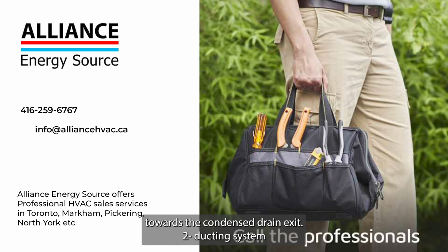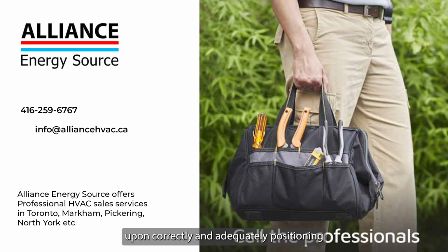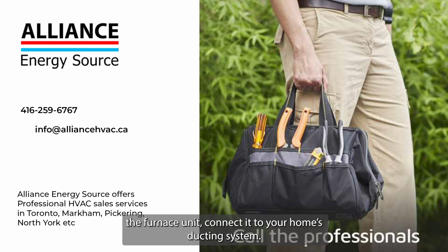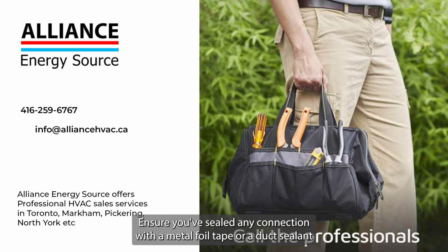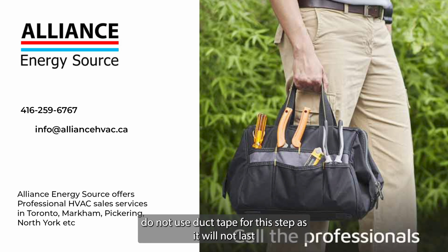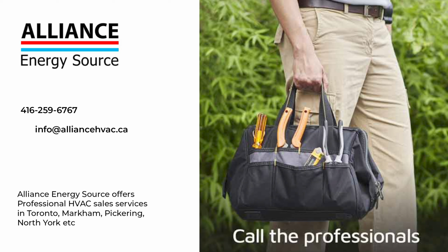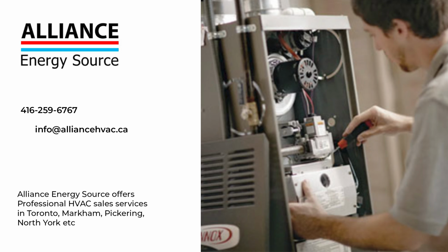2. Ducting system. Upon correctly and adequately positioning the furnace unit, connect it to your home's ducting system. Ensure you've sealed any connection with a metal foil tape or a duct sealant. Do not use duct tape for this step as it will not last. 3. Vent pipes. Next, install intake and exhaust pipes.